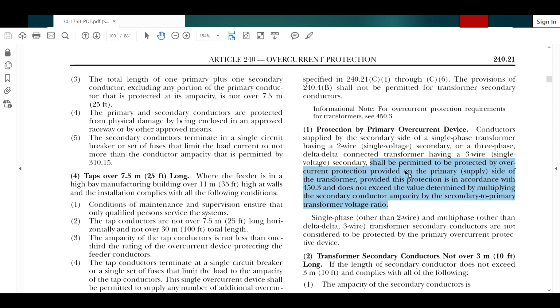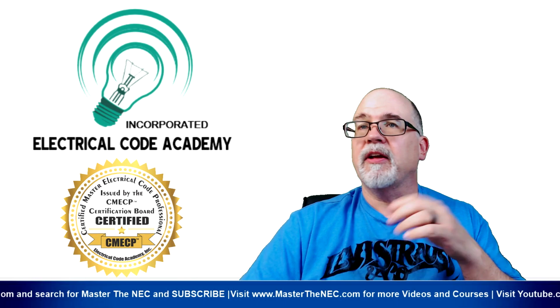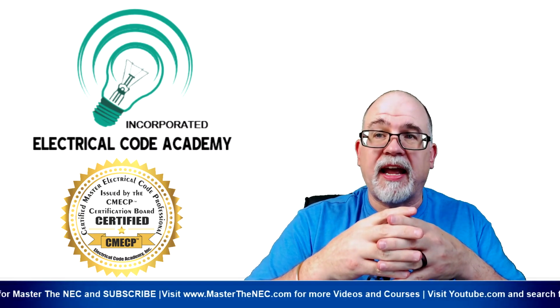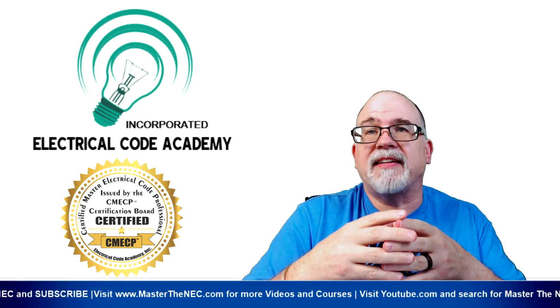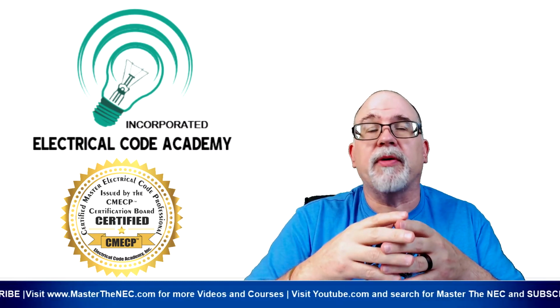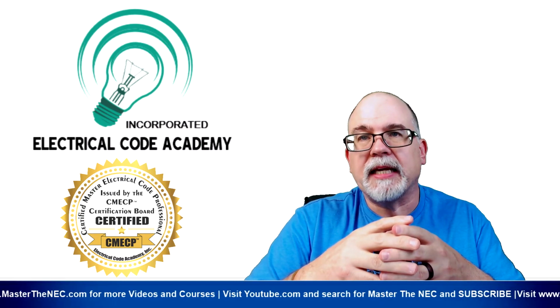Okay, so we're not even going to get into that because this does not matter unless you're dealing with a single phase 2-wire with a single voltage secondary, or a 3-phase delta to delta connected transformer with a 3-wire secondary that has only a single voltage like a 480 or 240. Other than that, it goes to remind you right here. It says single phase and multi-phase, 3-phase transformer secondary conductors are not considered to be protected by the primary overcurrent protection device. So it only applies to these unique transformer setups. Okay, so that is so obscure that you're not going to see that on any code exam. Yes, you might deal with it if you're doing a delta to delta. Then it might, and it's a three-wire output, and it's only one voltage scheme. It might happen. Okay, then that primary.